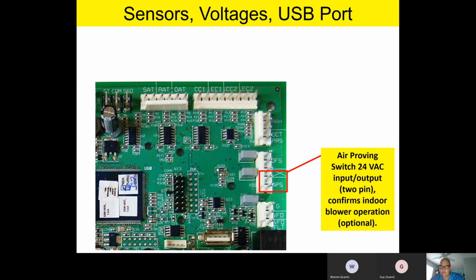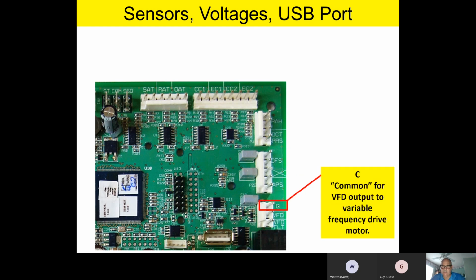And again, this is a 24 volt input output, and it confirms blower operation. And again, it doesn't come from the factory with this unless it's ordered, or more specifically, if you have a building requirement for this, this is where you'd put an air proving switch if that was required by the engineer or the architect. As we move down the board, we have a C.